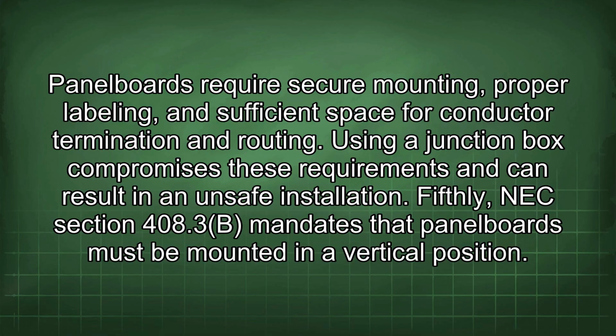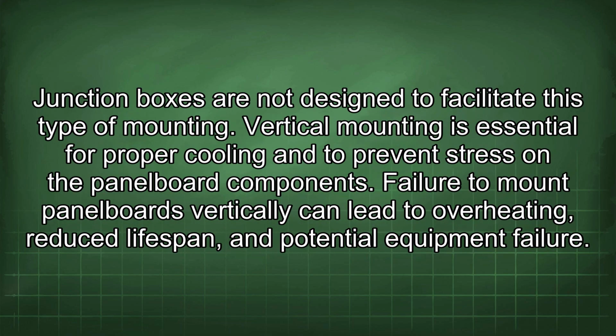Fifthly, NEC Section 408.3(B) mandates that panel boards must be mounted in a vertical position. Junction boxes are not designed to facilitate this type of mounting. Vertical mounting is essential for proper cooling and to prevent stress on the panel board components. Failure to mount panel boards vertically can lead to overheating, reduced lifespan, and potential equipment failure.